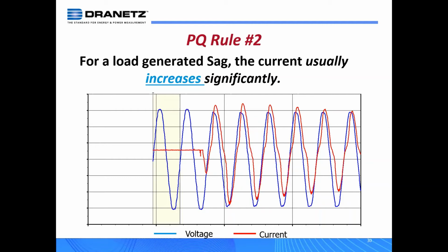So if you're monitoring both voltage and current, in this case, it would say this is a downstream SAG and give you the details of the SAG, how long it was out and its magnitude, or an upstream. So it'll put it right in the data stream. So you don't have to remember these rules of thumb. Okay, if you're using our Vista level instrument, that's entry level, you have to remember these rules. Guide and above, it'll provide that. And we also have these abilities with the SAG directivity answer module in our fixed systems, in our PQView DE and our PQView software.